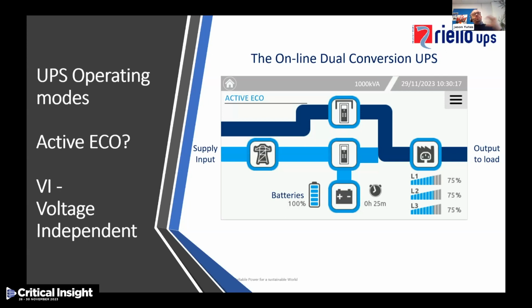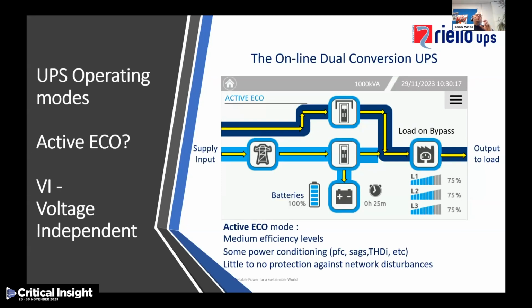It's very similar to eco mode in that the load is being powered directly through the mains supply. But this time, the dual conversion process is still operating, and the inverter is actually running in parallel with the bypass line, so it's operating like a power conditioner. By doing that, it can provide some forms of power conditioning, but it doesn't provide the protection that an online system does. So active eco mode provides a medium level of efficiency, somewhere between eco mode and online mode. It does offer some power conditioning in terms of power factor correction, sags, THDI correction, and so on. But again, because of this direct connection, it offers little to no protection against network disturbances, so again, it's not a favorite choice.